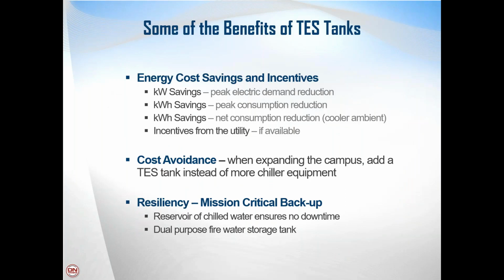And every one of the thermal energy storage tanks that we've ever built over the last 40 years had to have some sort of financial benefit for that owner. And I'm listing here several of those financial benefits that owners seek out or recognize when they add a thermal storage tank to their system. There's usually an energy cost savings component of that, where the owner has a time of use electric rate where they have lower cost of power during off-peak hours, where they could run their chiller equipment during those off-peak hours at a lower cost, and then turn off their equipment during the peak time of the day. That usually saves both on the kW, the demand side of their electric bill, and the kWh consumption side of their bill.